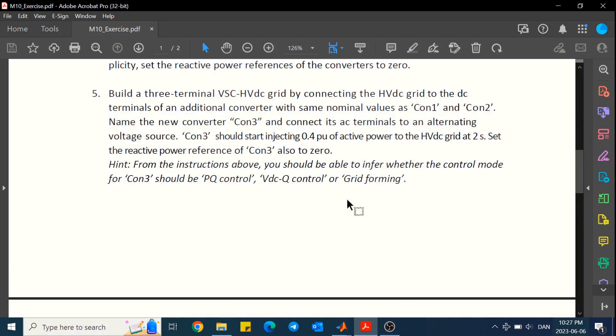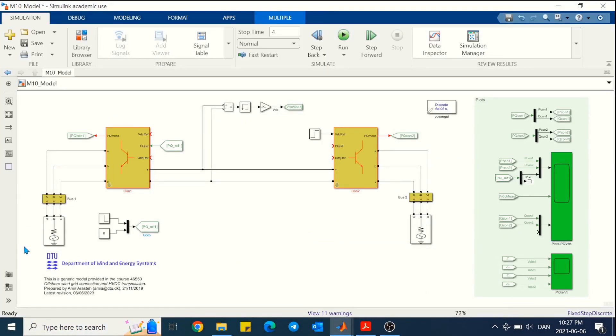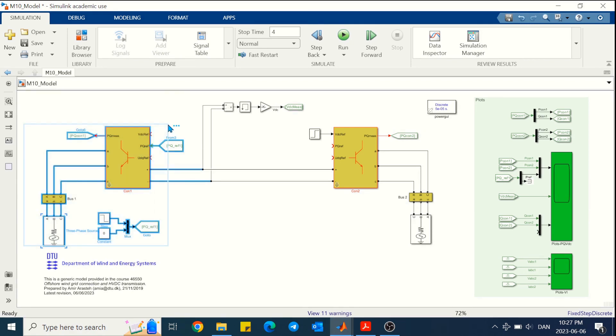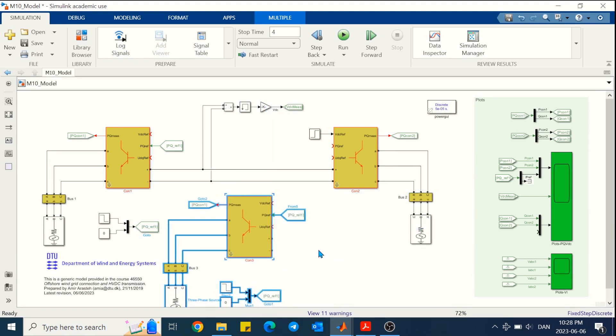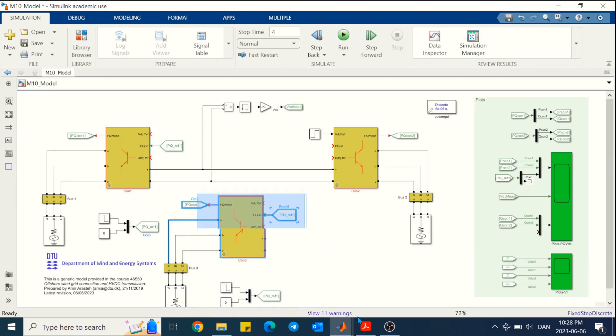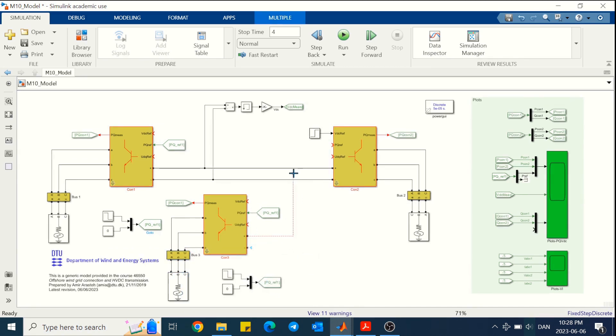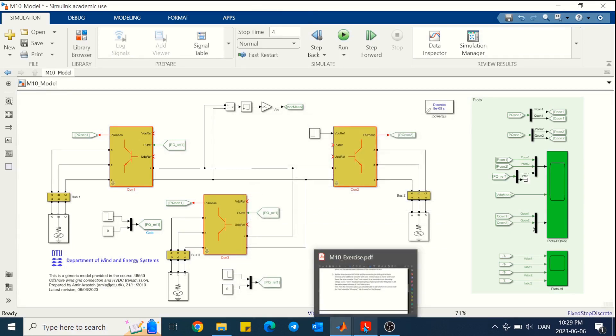In the next step we are asked to build a three-terminal HVDC grid and name the new converter as CON3. For that we can simply copy and paste one of the converters and connect it to the DC link, making sure about the polarity — positive to positive, negative to negative. Concerning the references, this converter is asked to inject 0.4 per unit of active power at t equal to 2 seconds, so we do the settings accordingly. Now we have converter 3 as well.